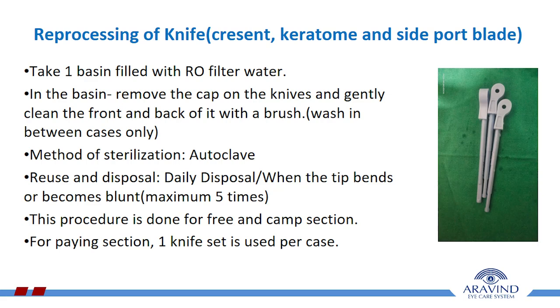Now we will see the reprocessing of knife, that is a crescent, keratome and a side port blade. Take one basin filled with RO filter water. In the basin, remove the cap on the knives and gently clean the front and back of it with a brush. Method of sterilization is autoclave. Reuse and disposal is daily disposal, or when the tip bends or becomes blunt, maximum 5 times we can use it. This procedure is done for free and camp section. For paying section, 1 knife is used per case.